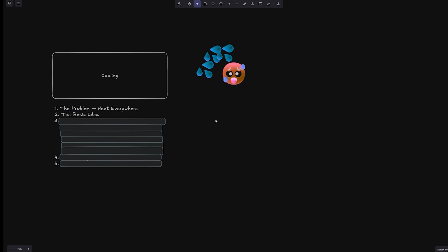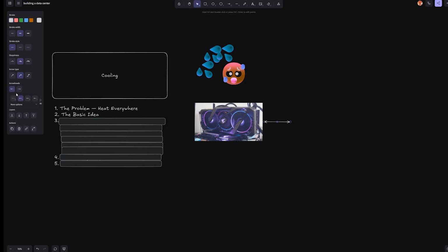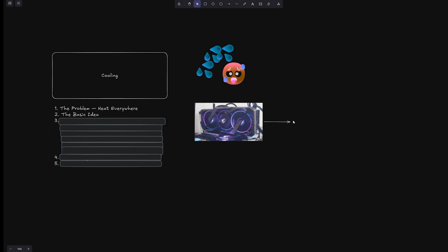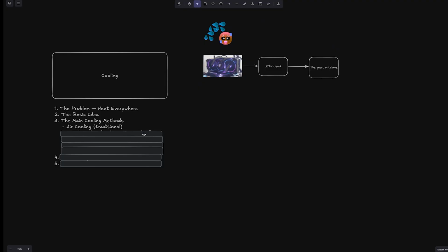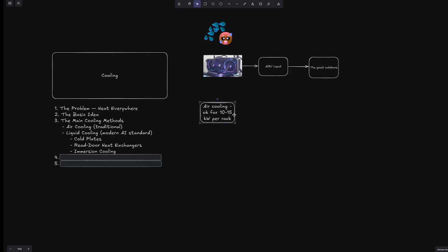The basic idea of cooling is that cooling is just heat transfer. Move heat from chips to air or liquid to the outdoors. AI data centers focus on doing this efficiently because cooling can consume up to 30 to 40% of total power if done badly. The main cooling methods used today are air cooling, which is the traditional way of cooling. We just blow cold air through the servers and exhaust the hot air out. Cold and hot aisles are separated to avoid mixing, and this works for 10 to 15 kilowatts per rack before inefficiency skyrockets. Fine for small labs, but not for dense AI clusters.